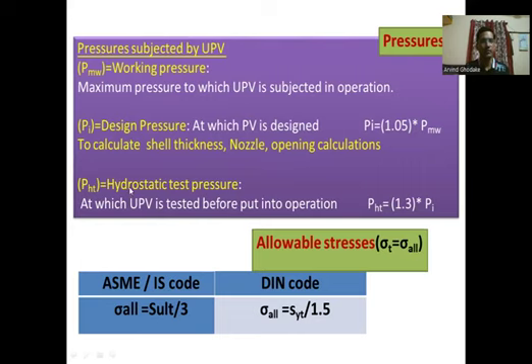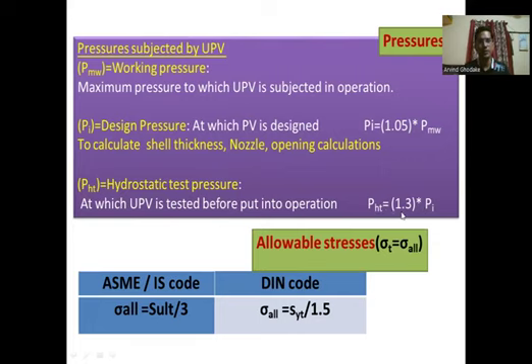Next is the hydrostatic test pressure — the pressure at which the unfired pressure vessel is tested before being put into operation. It is denoted by PHT and is given as 1.3 times the internal or design pressure: PHT = 1.3 × PI.